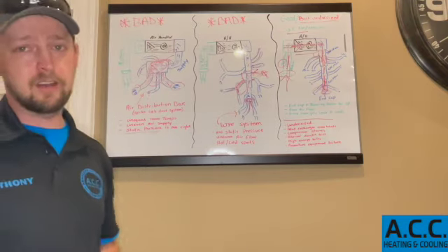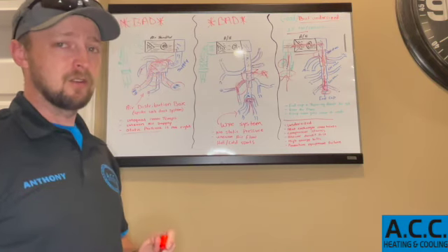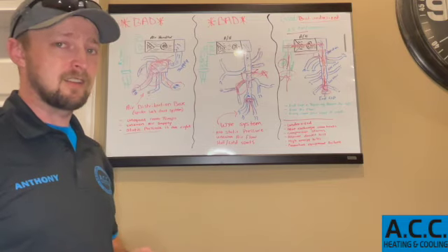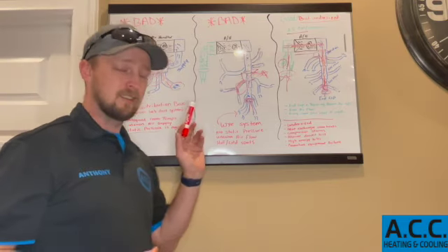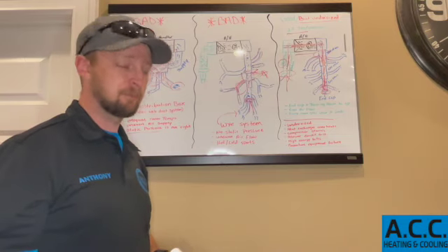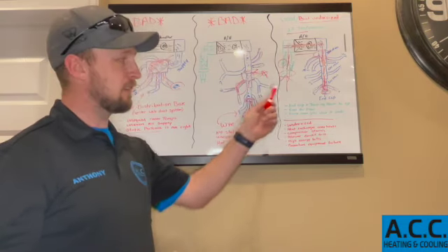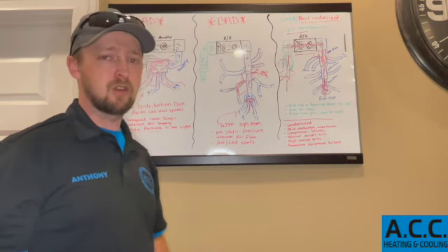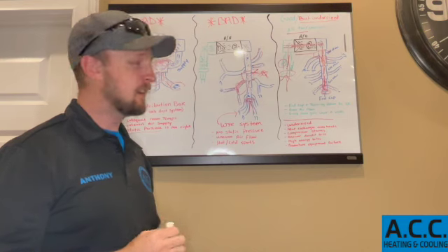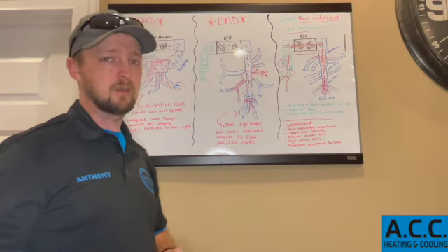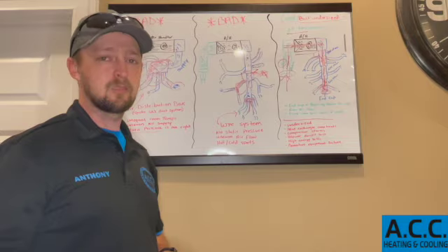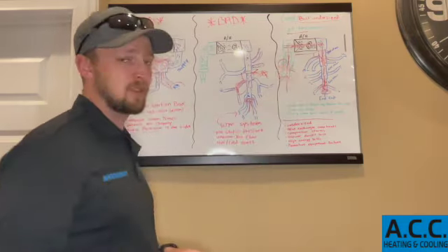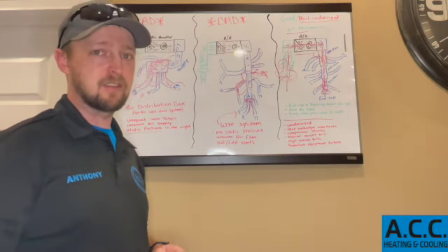Nobody ever talks about airflow, and there's a few companies out there that will, and they do it the right way. I will say that. But there's a lot more companies out there that will come to your house and tell you to replace your system, but they can't identify what made the system fail in the first place. If your system was 8 years old and the compressor went out and you're replacing it, I guarantee you it wasn't that compressor's fault. Something behind the scenes was making that compressor fail. And 9 times out of 10, it's this return, not having enough return air to the system.